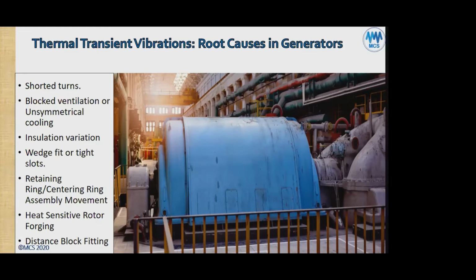Shorted turns, blocked ventilation holes, unsymmetrical cooling, insulation variation, wedges not fitting well or tight slots, retaining ring, centering ring, assembly movement, heat-sensitive rotor forgings, distance block not fitting well.